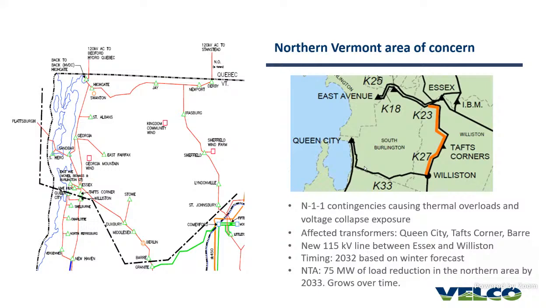This overload happens because we are sending power to the northern area. There's a major load center around Taft Corner, Essex, East Avenue, and all of that load needs to be served by the system. When we lose that line, you see the issue there. By reducing the load north of that line, we relieve the overload we saw. That's how the non-transmission alternative works, and if we do that, we would not need to build the line between Essex and Williston.